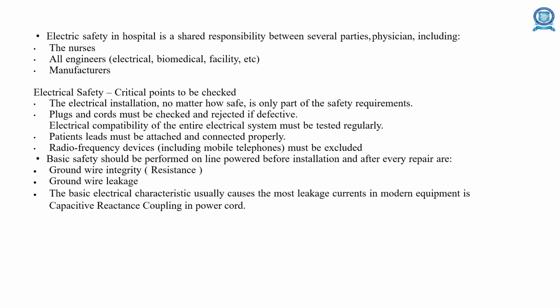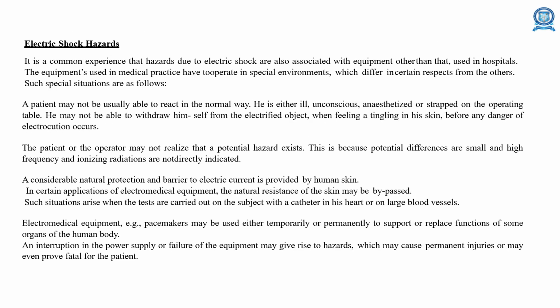Electrical safety in hospitals is a shared responsibility between several parties: physicians, including the nurses, engineers and the manufacturers. The critical points to be checked in electrical safety: the electrical installation, no matter how safe, is only part of the safety requirements. Plugs and cords must be checked and rejected if defective. Patients' leads must be attached and connected properly. Radio frequency devices must be excluded. Ground wire integrity, ground wire leakage, and the basic electrical characteristics usually cause the most leakage currents.